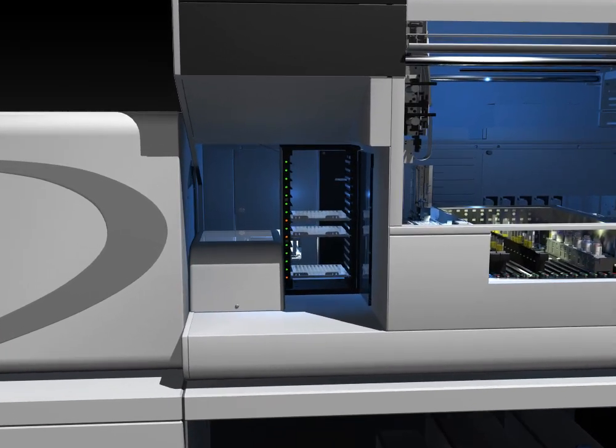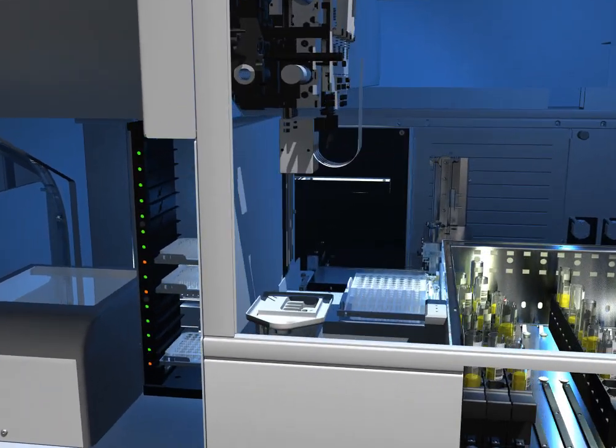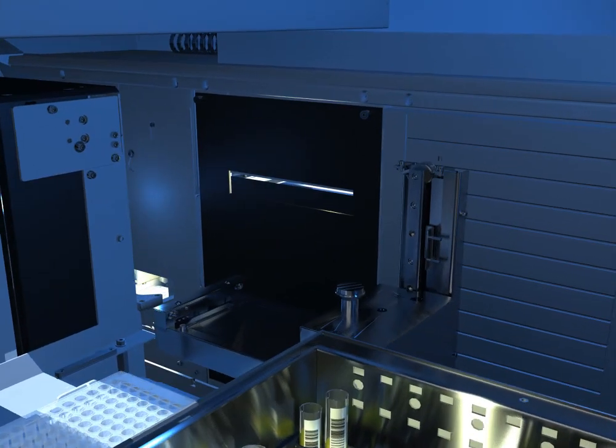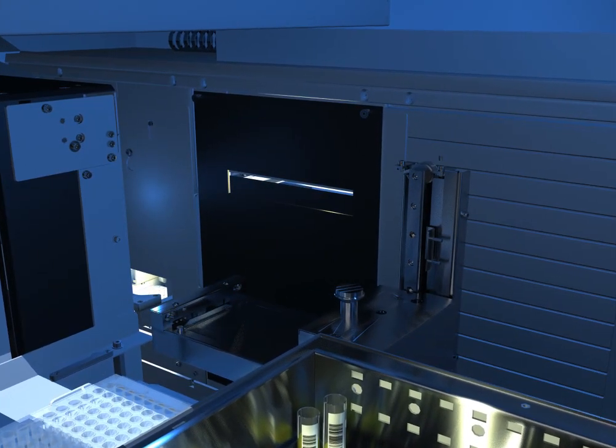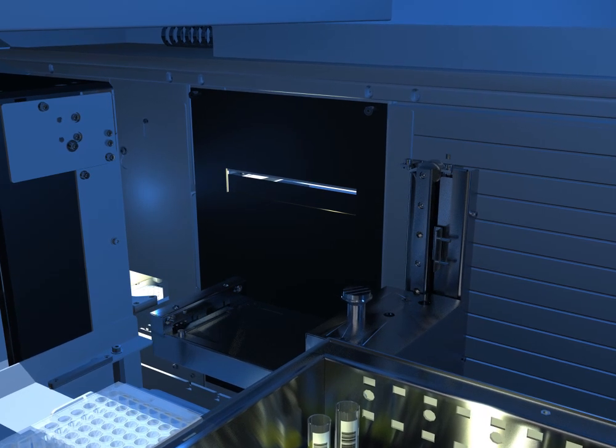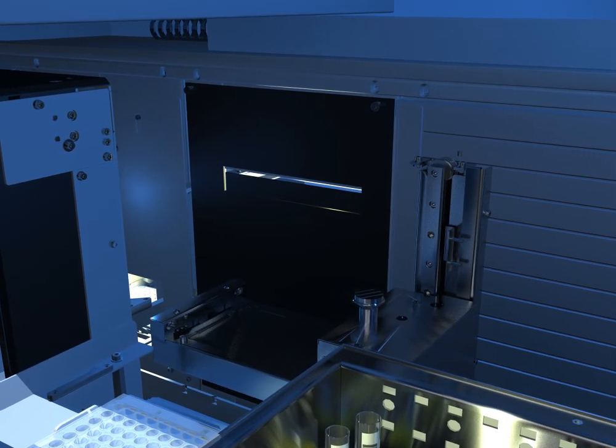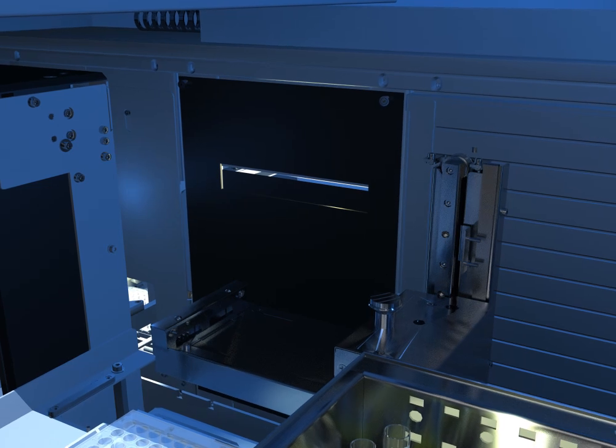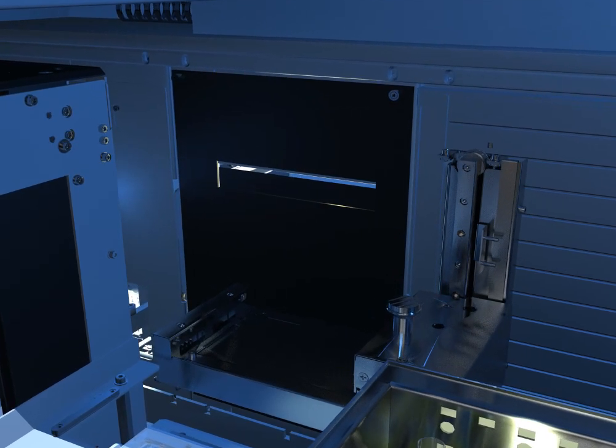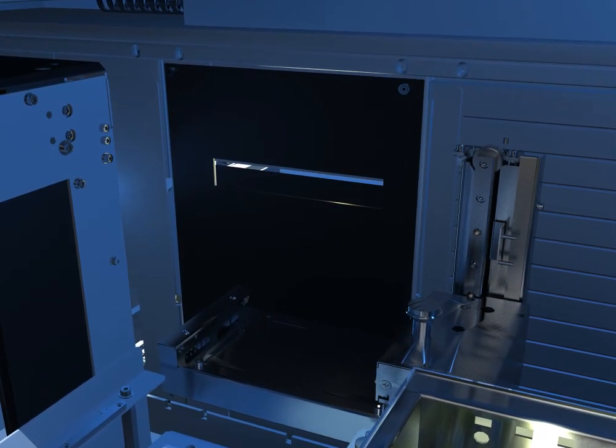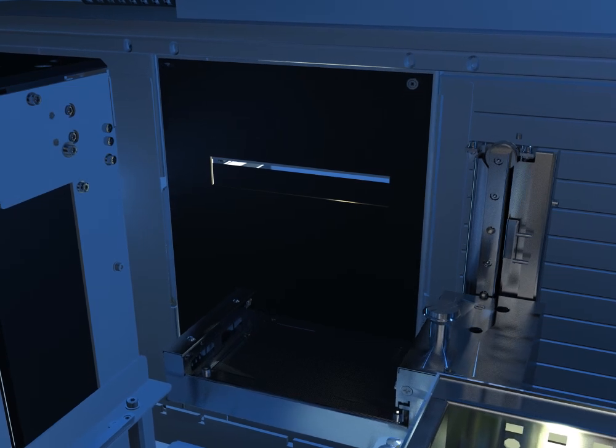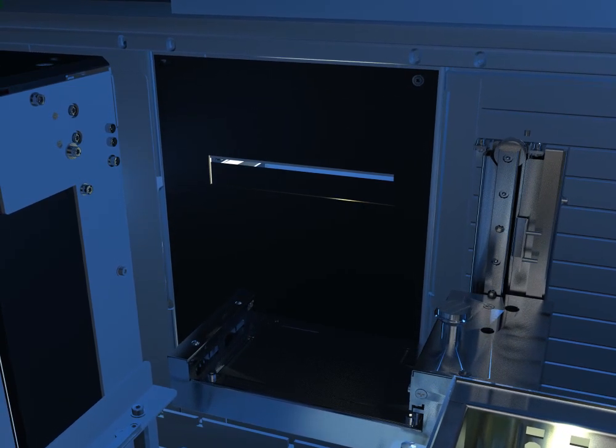Behind the microplate loading tower is Neo's reader. The reader is utilized to check plates prior to testing for process control steps such as color verification checks and for reading results. We use 2 CCD cameras on the Neo. They take digital photographs of the microplate to use for interpretation. By interpreting the pixels of the well reactions, Neo makes an interpretation. We call this an image analysis reader.